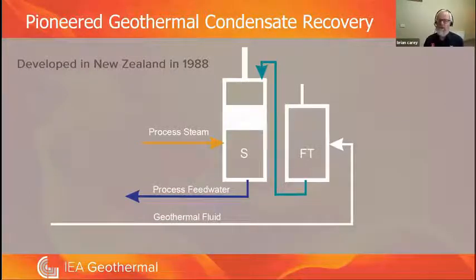Now at Kawerau, there was a really interesting development pioneered called geothermal condensate recovery. What had been happening at Kawerau, the geothermal steam had been used to power the industry, but once it had been condensed down to condensate, the fluid was just discharged to the surface. The Kawerau engineers decided they could actually recover that geothermal condensate. So they developed this system of flash tanks and cleaning columns called stripper vessels, where the geothermal steam condensate, which is low in minerals but high in gases, is fed through these two vessels, and it comes out clean enough to be process feed water for an industrial boiler. So this process essentially treats geothermal condensate, takes the gases out of it, and provides low mineral, high pH fluid.